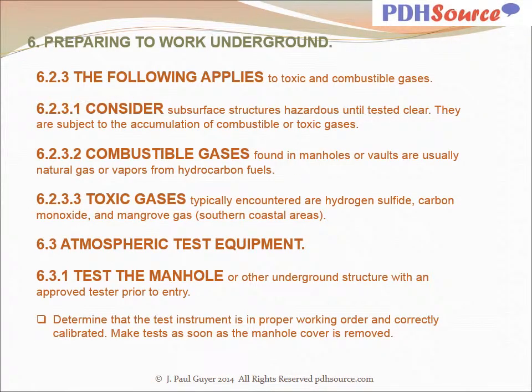The following applies to toxic and combustible gases. Consider subsurface structures hazardous until tested clear. They are subject to the accumulation of combustible or toxic gases. Combustible gases found in manholes or vaults are usually natural gas or vapors from hydrocarbon fuels. Toxic gases typically encountered are hydrogen sulfide, carbon monoxide, and mangrove gas in southern coastal areas. Test the manhole or other underground structure with an approved tester prior to entry. Determine that the test instrument is in proper working order and correctly calibrated. Make tests as soon as the manhole cover is removed.